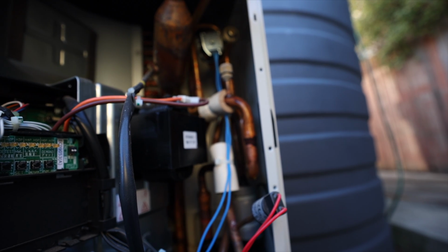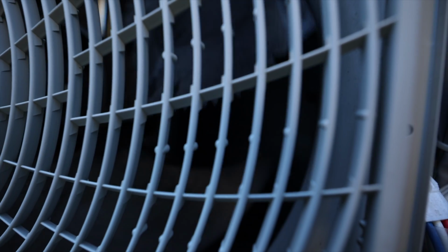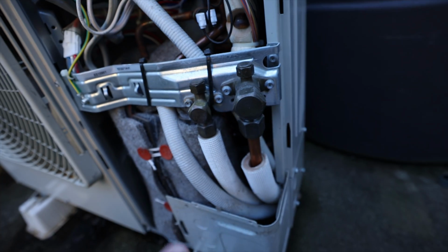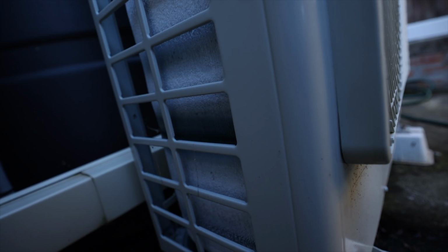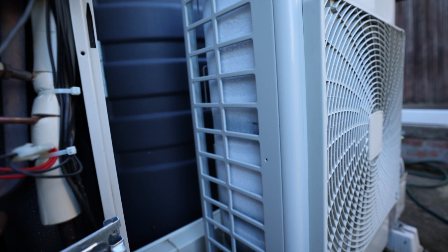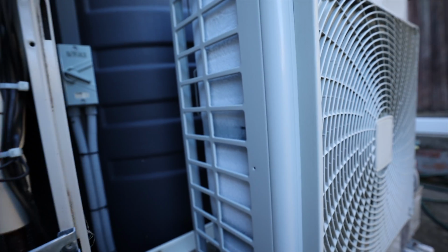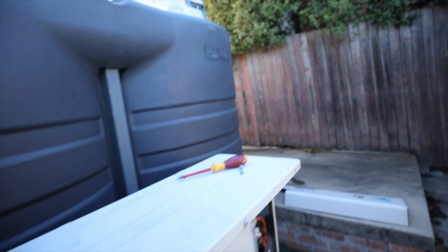Gas has gone to the inside now, and the outdoor fan has just turned off, so it's stopped spinning. The compressor is starting to speed up, sending the cold gas inside. If we look at the coil, it should already start melting. Down the bottom there, we can see that it's starting to melt, and we'll start getting water pouring out of the bottom of the unit. We'll try and capture that.